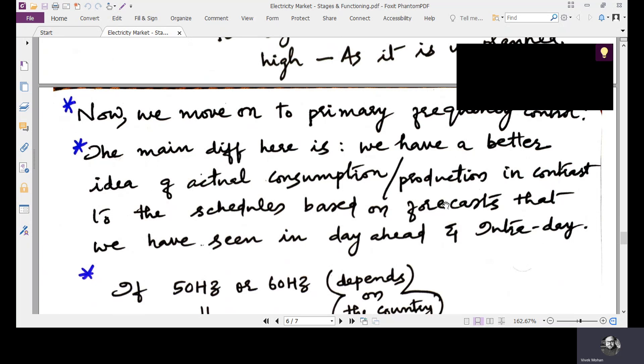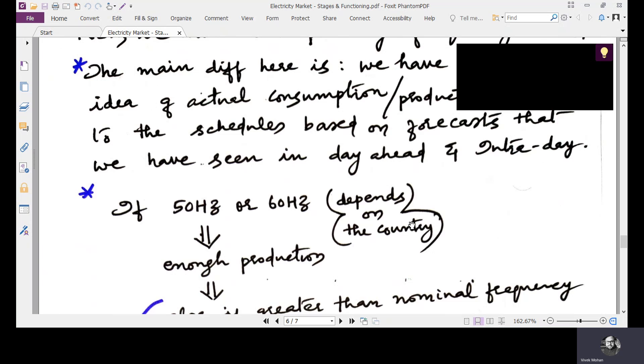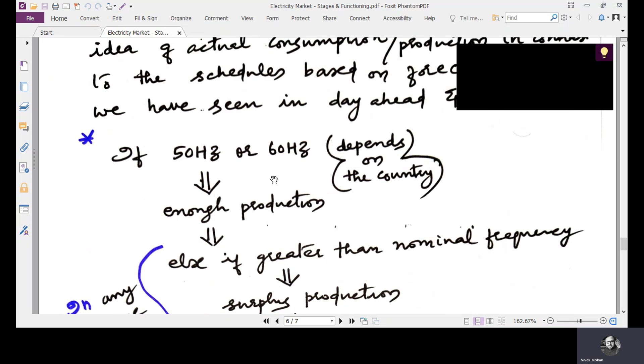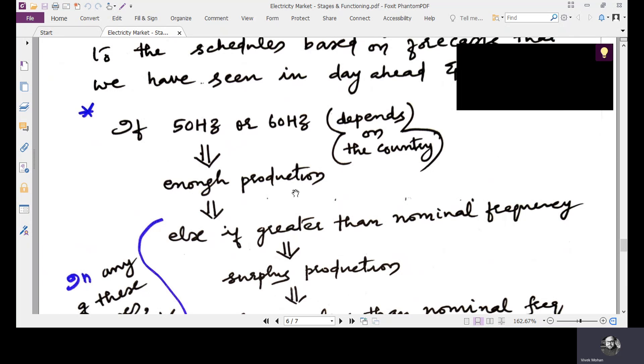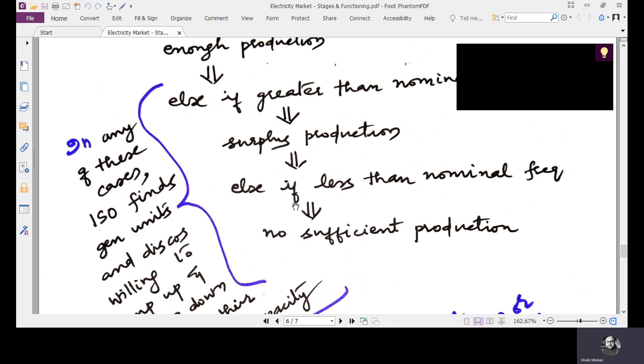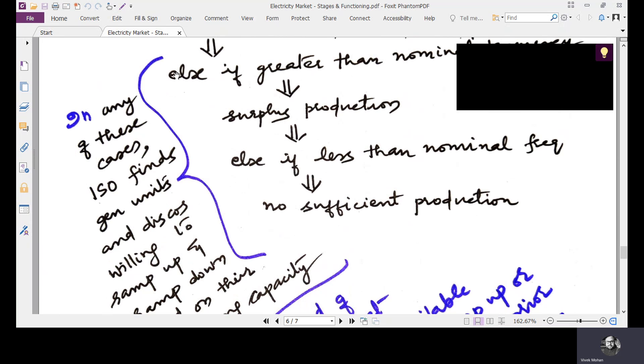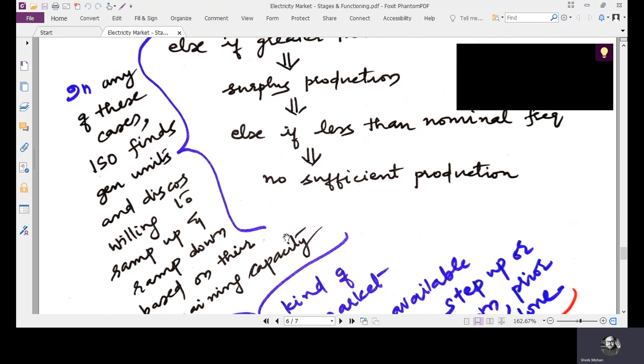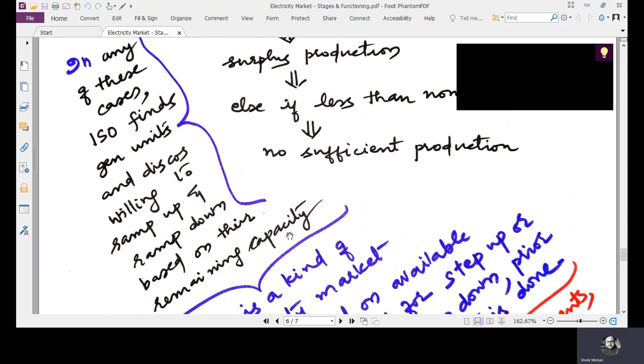The assessment of the demand-generation balance is done based on frequency measurement. If the system operates at nominal frequency (50 Hz or 60 Hz depending on the country), enough production is present. If frequency is above nominal, there is surplus production; if below nominal, production is insufficient. In any of these cases, the ISO finds generating units and distribution companies willing to ramp up or ramp down based on their remaining capacity.